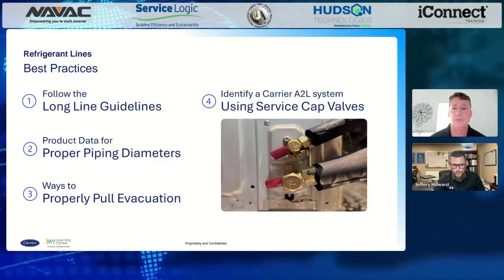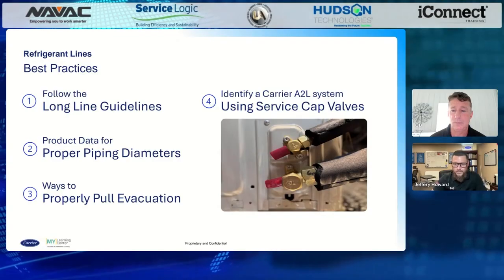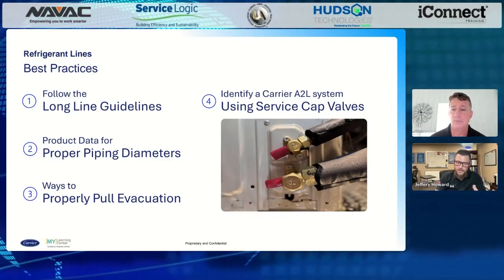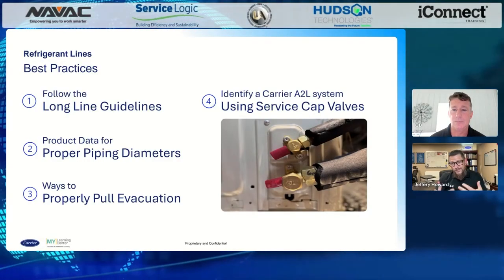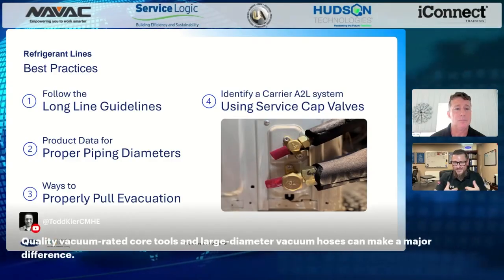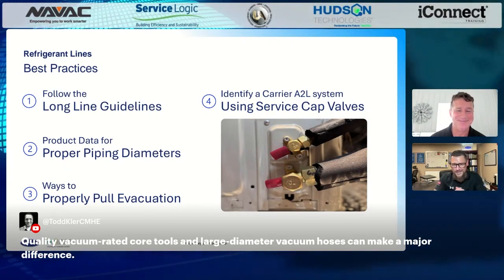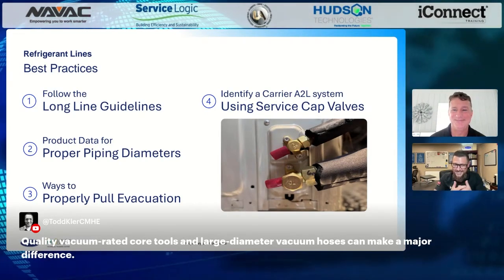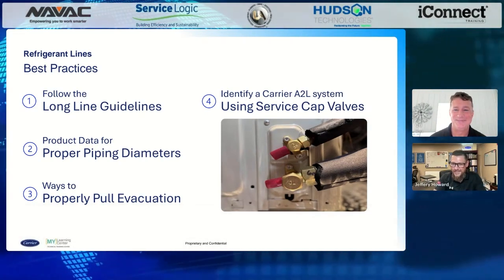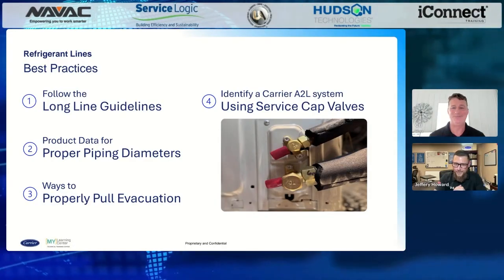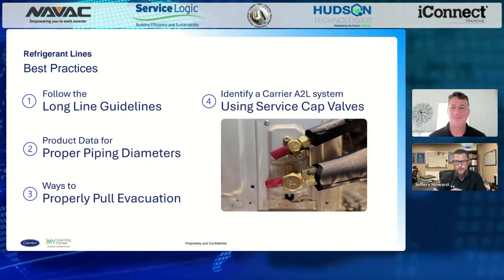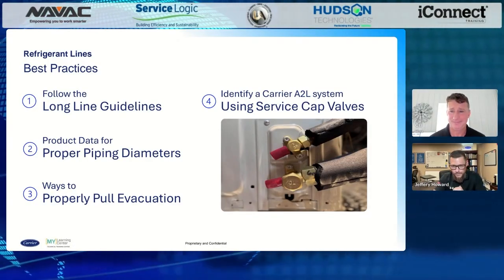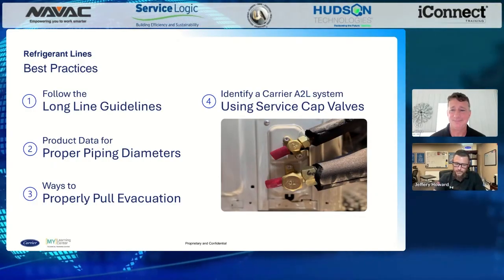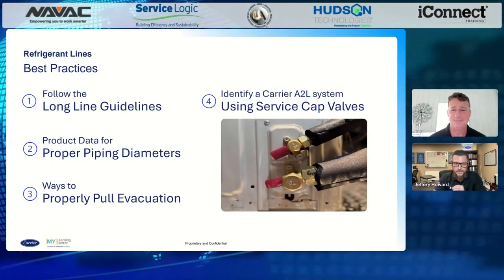When we talk about properly pulling that vacuum with a large diameter hose, I can tell you from experience that if you run through your manifold and gauge set with a 9 CFM vacuum pump, are you really pulling 9 CFM? No. You can actually finish quicker with a smaller pump, like a 2 CFM, if it's connected properly to your system.